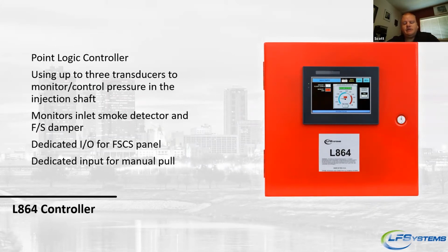It uses, like I said, up to 3 transducers to monitor the pressure in the shaft. Now, one good thing about this is you can monitor the pressure based off high pressure, low pressure, or it can take an average of the 3. This can be determined before install, but it can also be field programmed and changed after it's been installed. It has monitors for the inlet of the fan for the smoke detector and fire smoke damper. It has a dedicated I/O for the FSCS and a dedicated input for the manual pull.